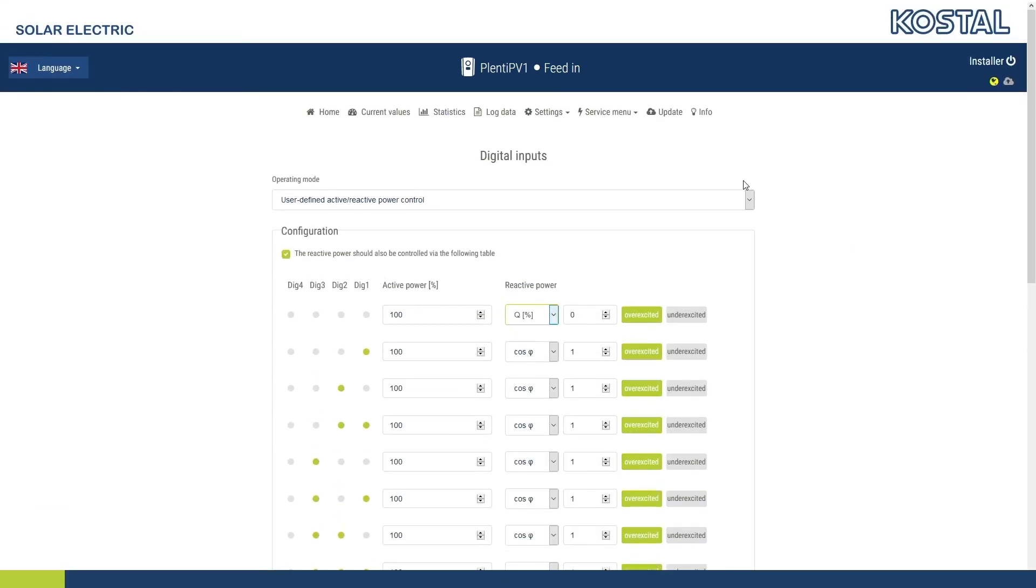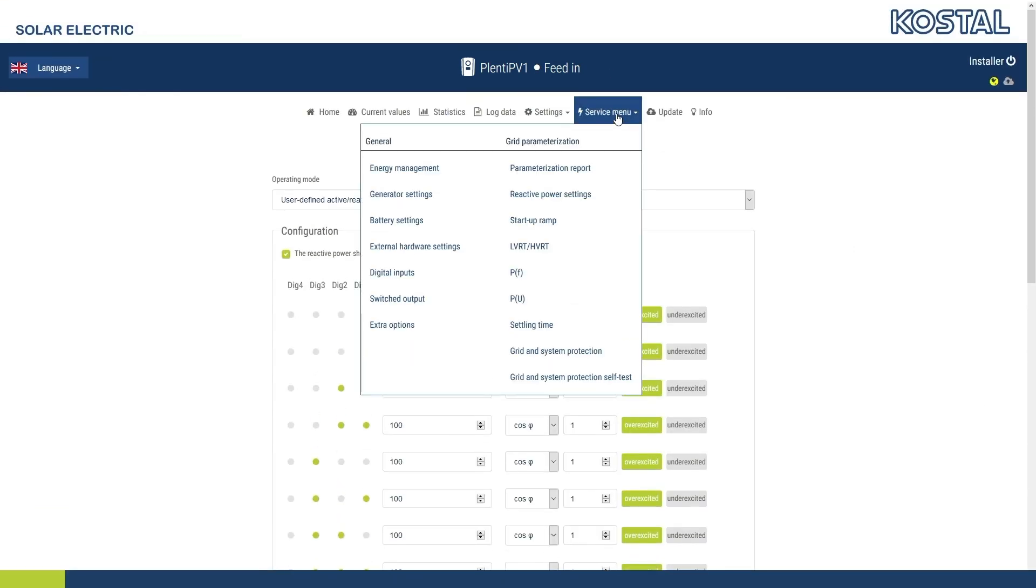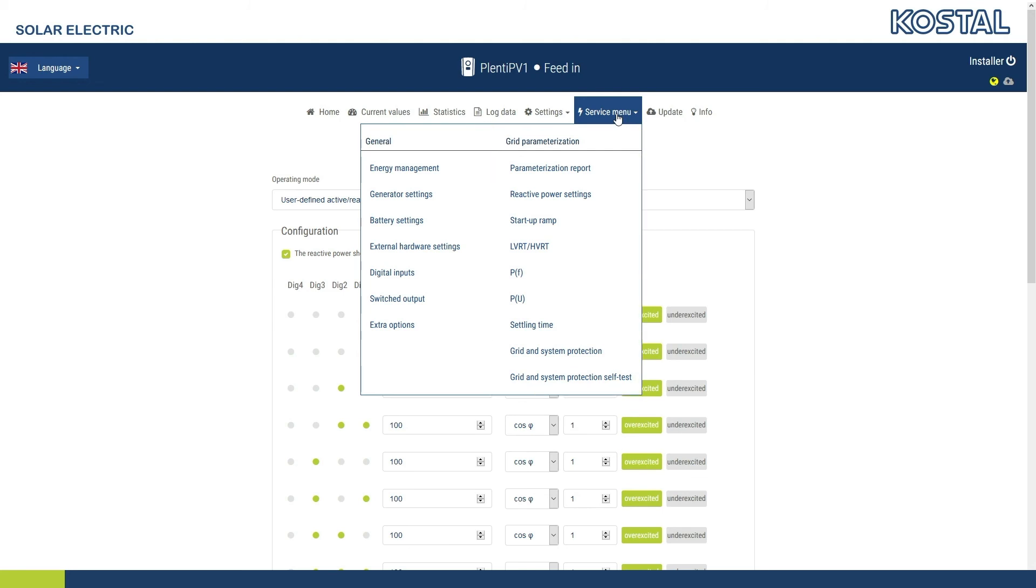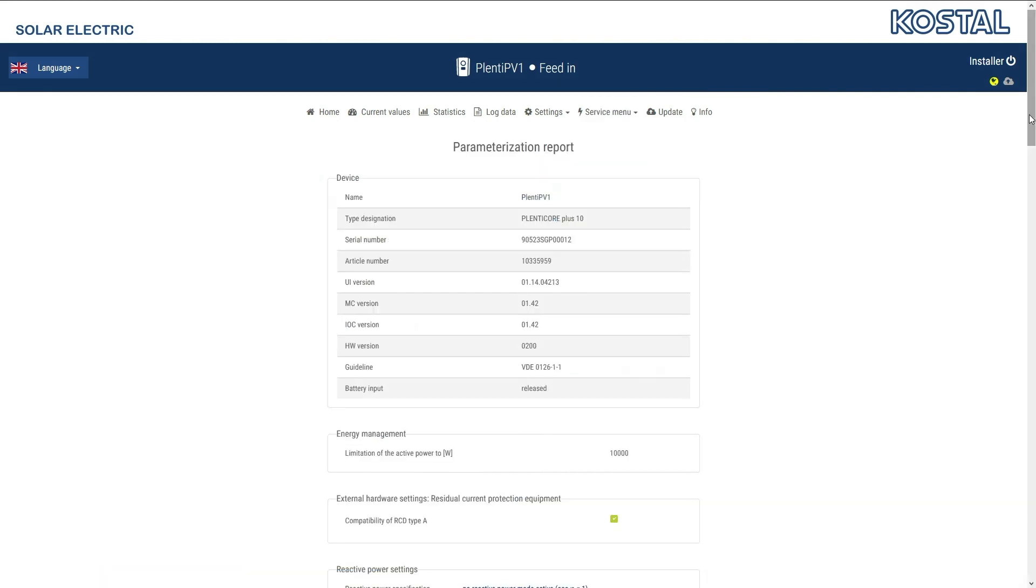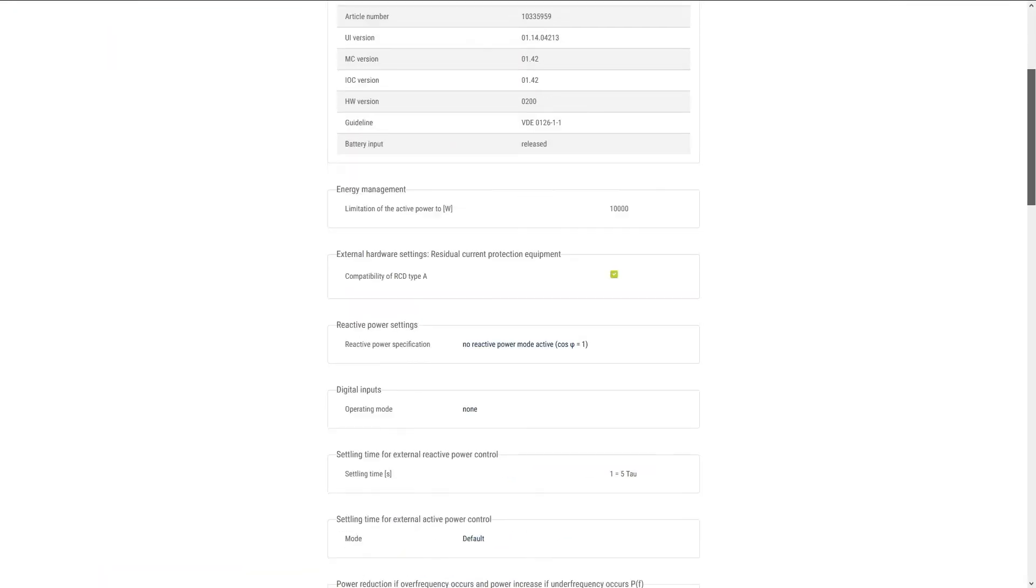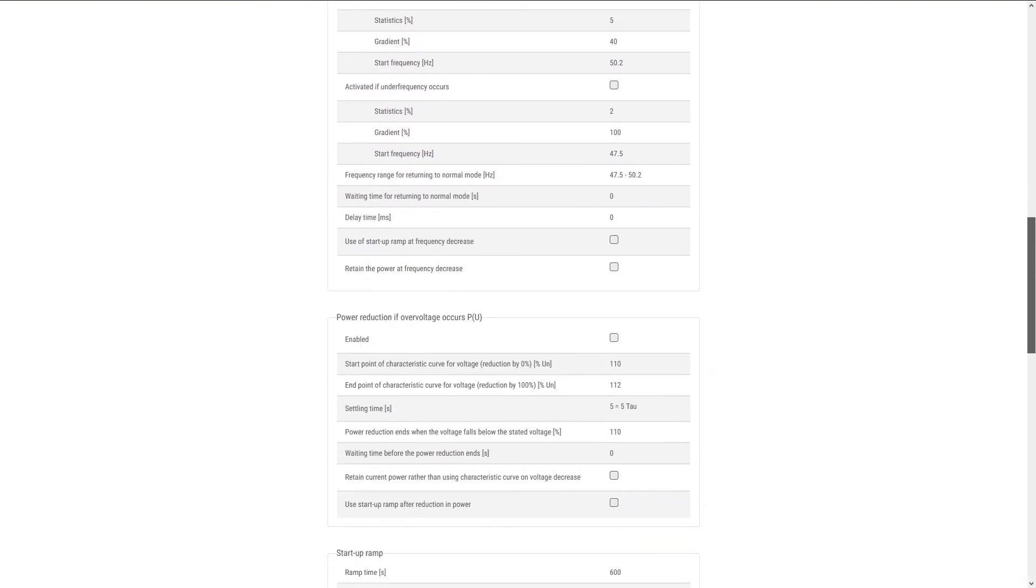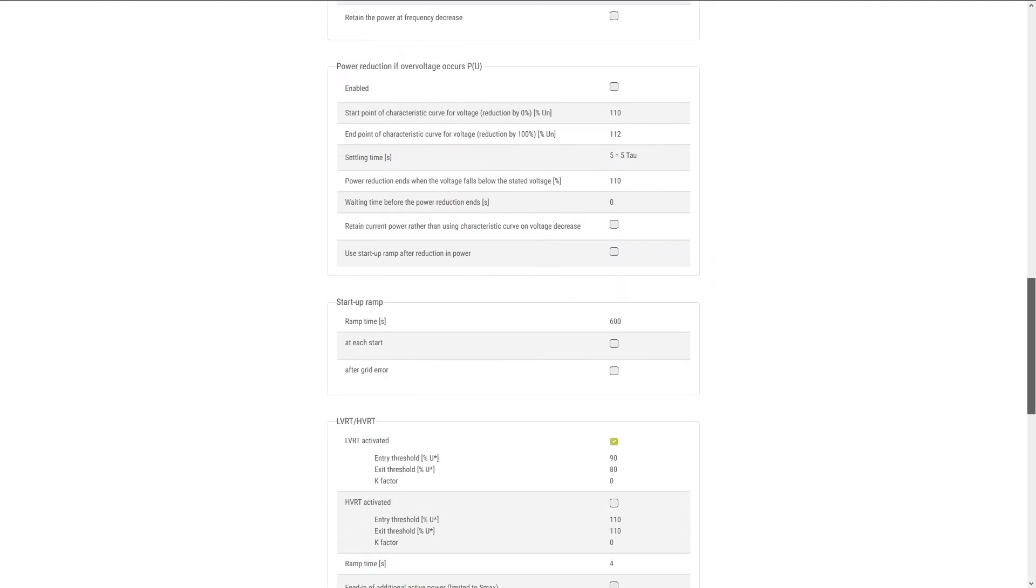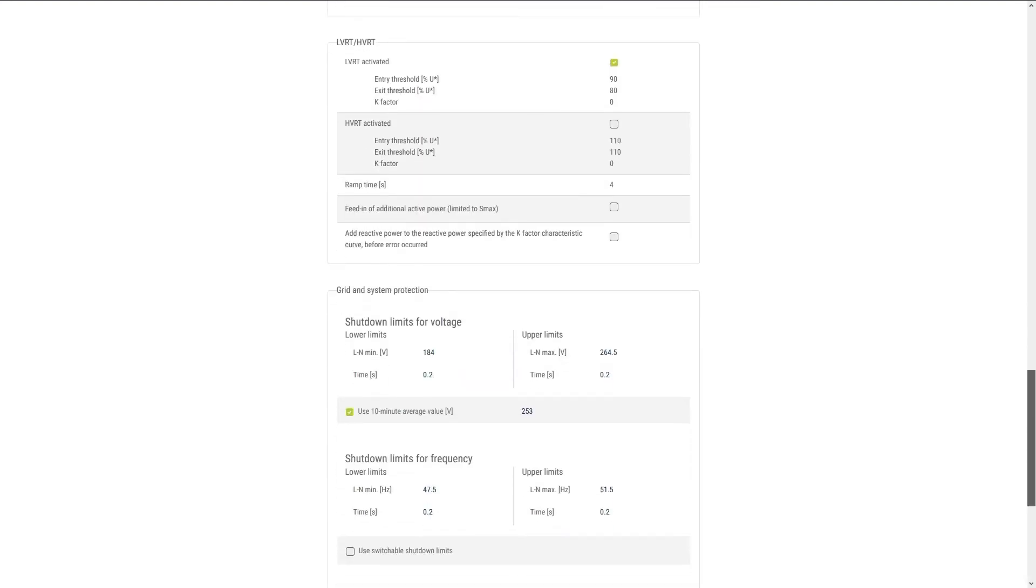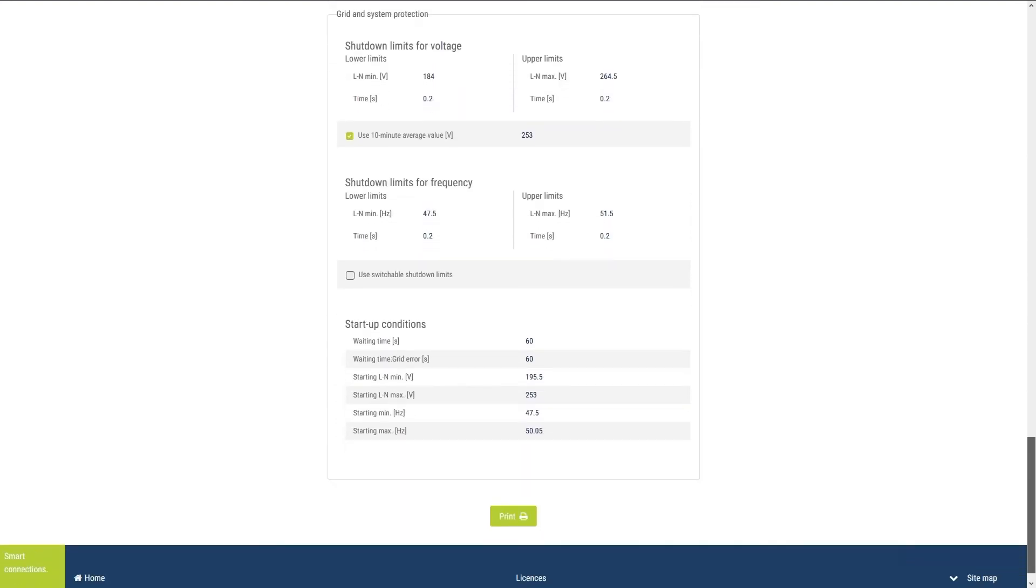On Request, the AC output parameters can be modified using the menu items in the Grid Parameterization area. Your grid operator will provide you with the relevant requirements. However, adjustments are not normally needed. The parameters in the selected guideline already match the country-specific requirements. The parameterization report provides an overview of the parameters set in the inverter. You can view and, if necessary, print out the report.